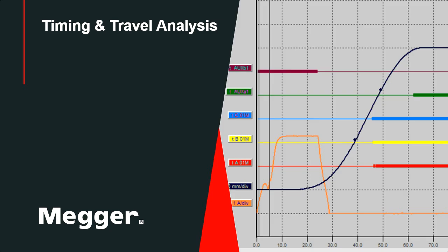So now that we've talked about some of the basic understanding and components of high voltage circuit breakers, we're going to talk a little bit about timing and travel analysis. So what is timing and travel analysis? Timing refers to the time in seconds, usually milliseconds, from the moment that the circuit breaker receives that pulse signal to either open or close from the protective relay or from the command from the unit itself. The operation is complete when the contacts reach their final resting place.